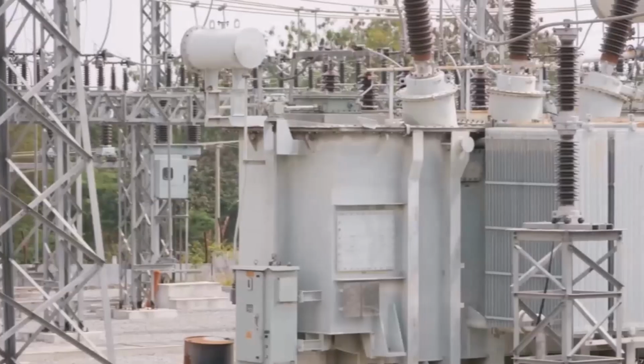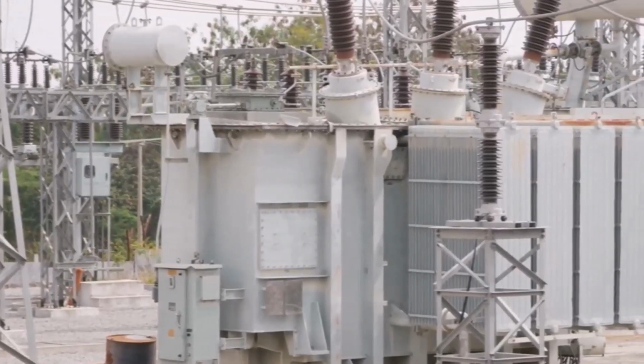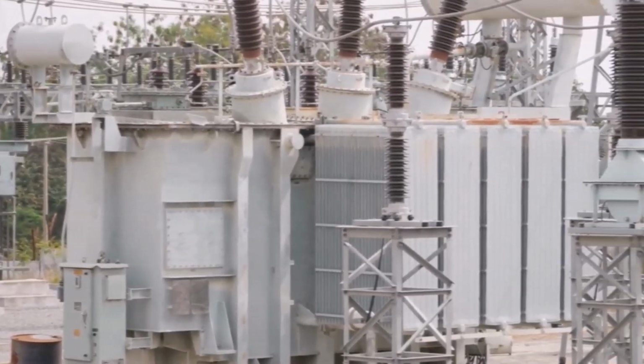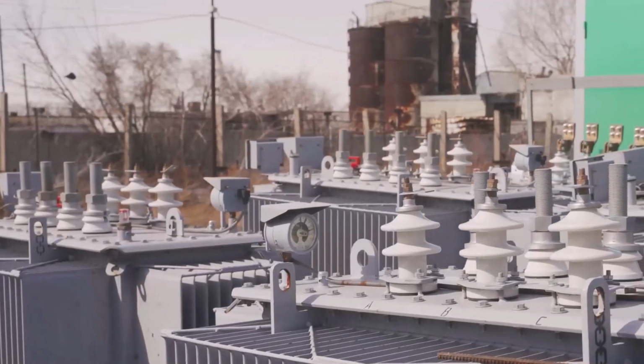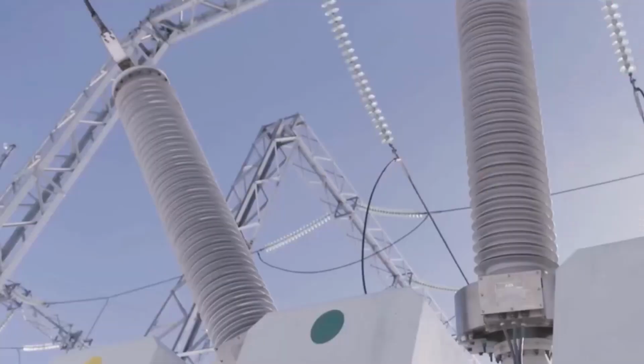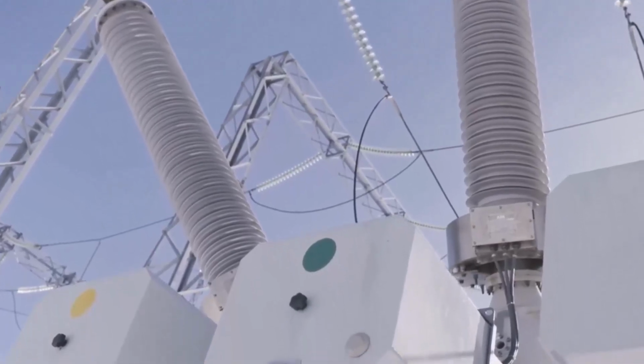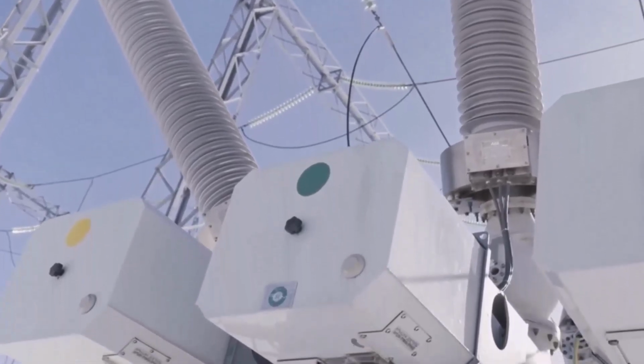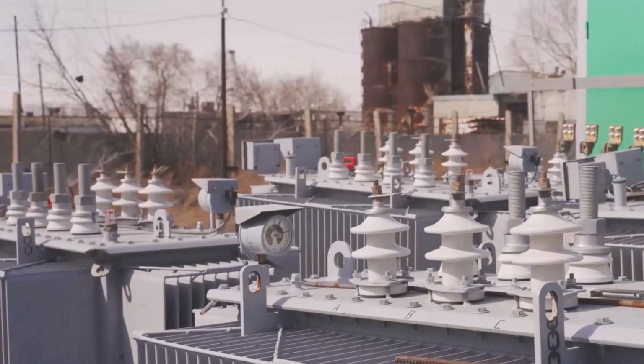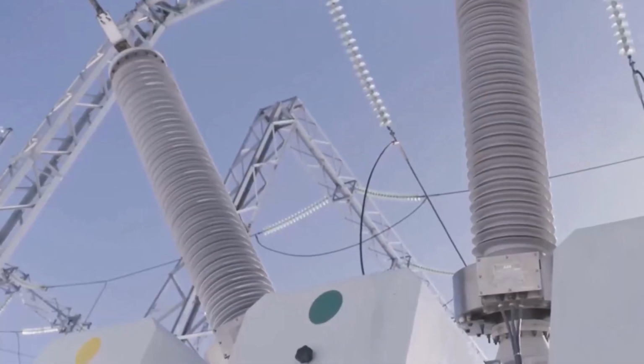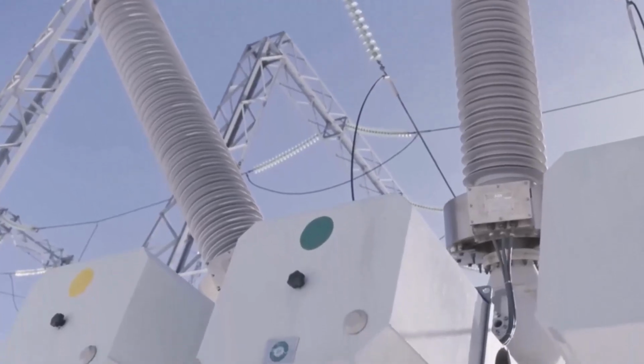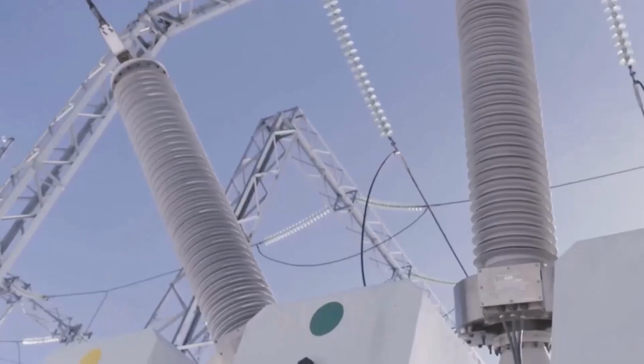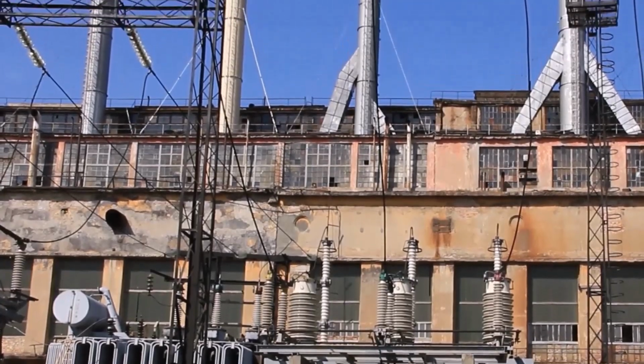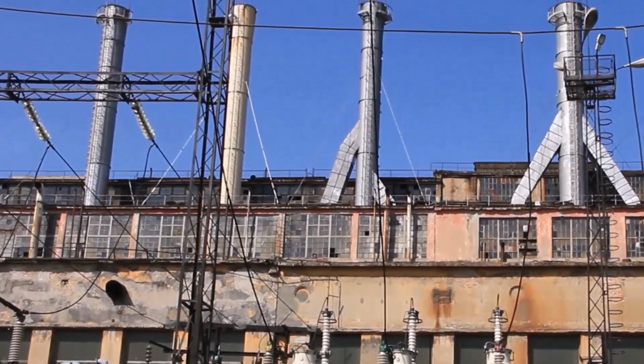A third very common place to find a delta setup is inside the windings of a transformer itself. Transformers often have different connection types on their primary or input and secondary or output sides. A very common configuration is a delta-Y transformer. In this setup, the high-voltage primary side is connected in delta to handle the incoming transmission voltage. The secondary side is then connected in a different configuration called a Y or star, which does have a neutral point. This allows the transformer to supply power to both three-phase industrial loads and single-phase residential loads, giving us the best of both worlds.